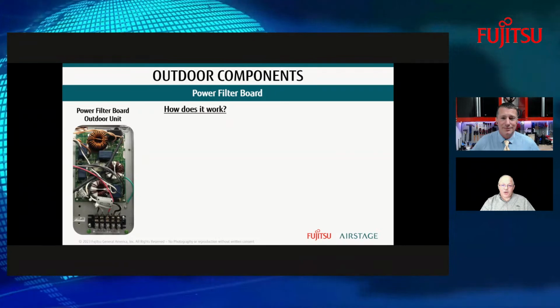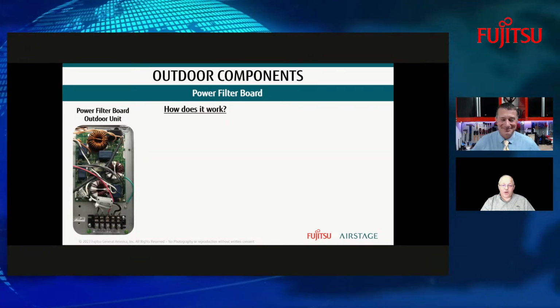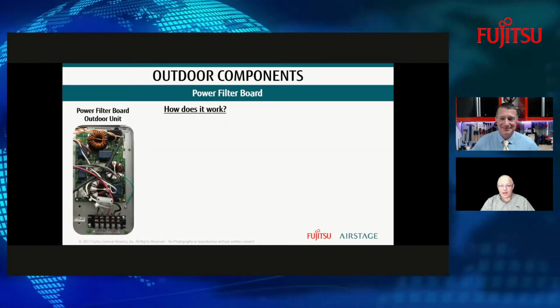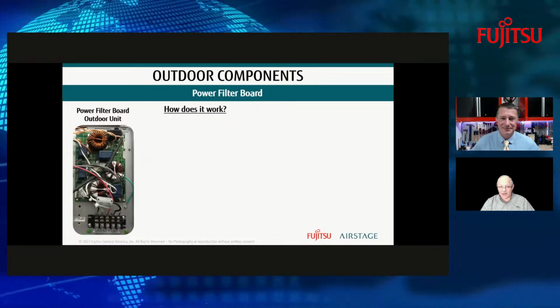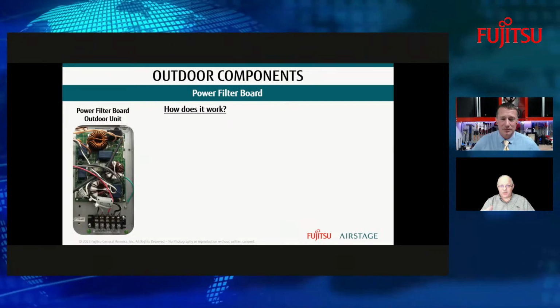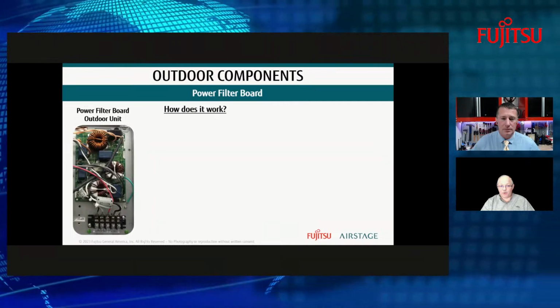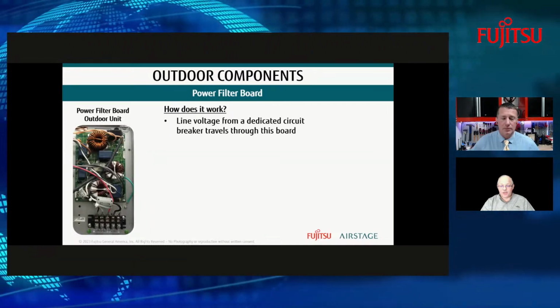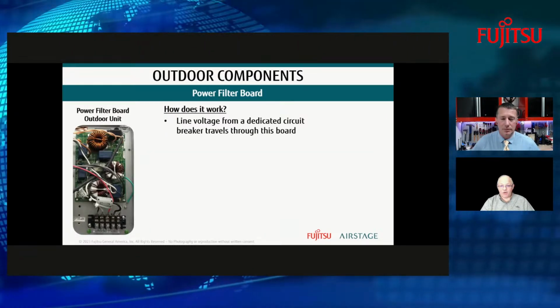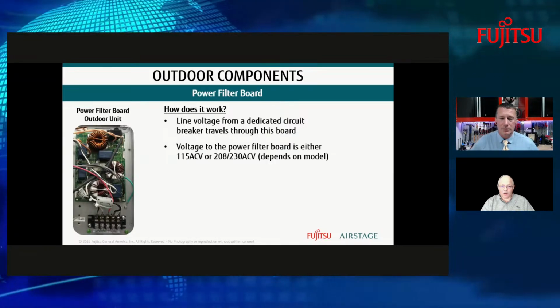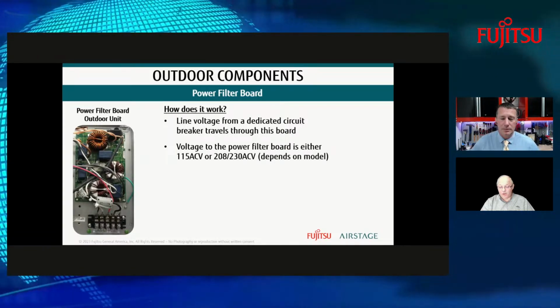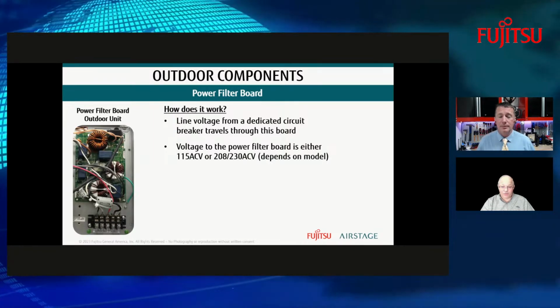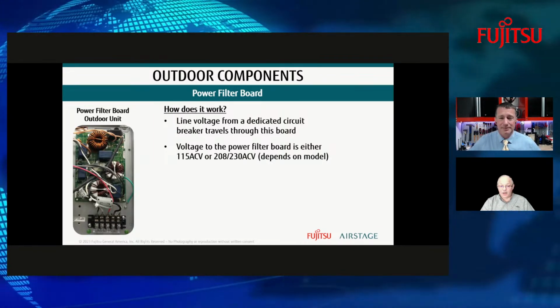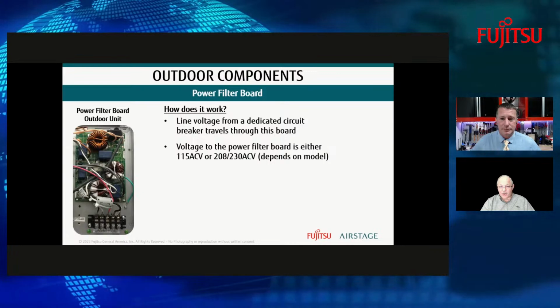So the big question always comes in, well, how does it work? So we're going to look at some of the components that are part of this process. Now, this is where the power first comes in. This is the power filter board that you see in the outdoor unit. So we have line voltage coming from our circuit breaker and into the board. Depending on the model of the outdoor unit, it could be a 115 volt or it could be a 230 volt. So that power is going to come in.